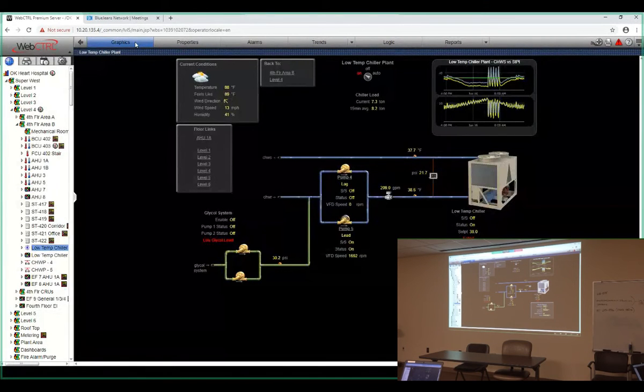The other thing that caught my eye is the differential pressure on the chill water supply and return, around 22 psi. Does that seem high? I'll have to look into that. I'm not sure. The other DPs were 2 and 3 pounds, I thought. The plant building supply is running at 27 psi. Is it? Okay. The chillers are running around 5 psi across the chill water barrel. Yeah, that's where I see it.